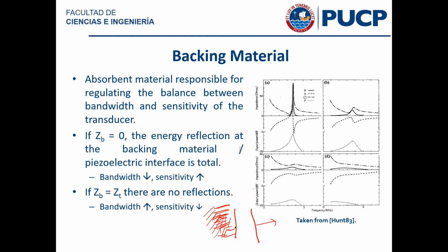And the reason for the backing material, imagine the case where the impedance of the backing material is exactly equal to the impedance of the piezoelectric element. And this is a piezoelectric element with some impedance. What would happen if I were to get my hands onto a backing material that has exactly the same impedance as the piezoelectric? What would happen? Who wants to participate?